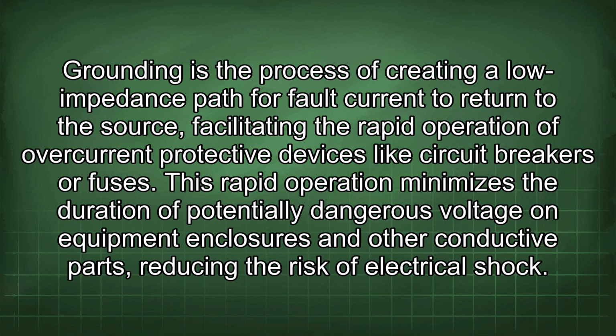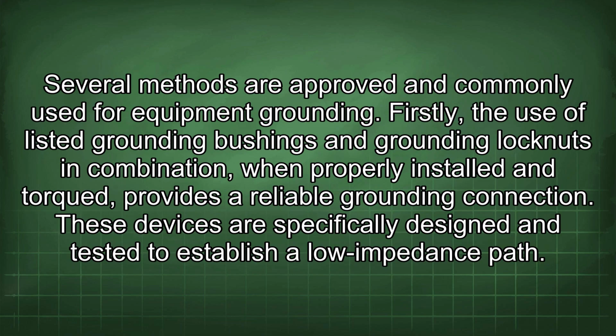Grounding is the process of creating a low impedance path for fault current to return to the source, facilitating the rapid operation of overcurrent protective devices like circuit breakers or fuses. This rapid operation minimizes the duration of potentially dangerous voltage on equipment enclosures and other conductive parts, reducing the risk of electrical shock. Several methods are approved and commonly used for equipment grounding.